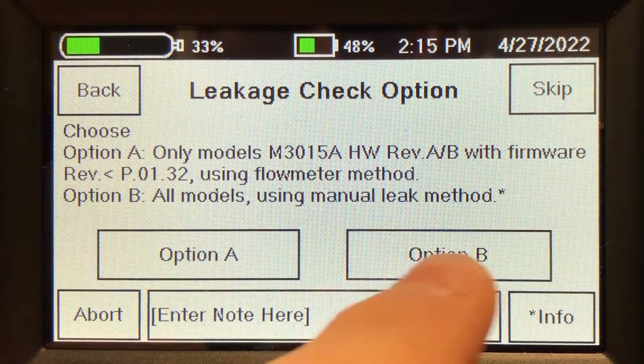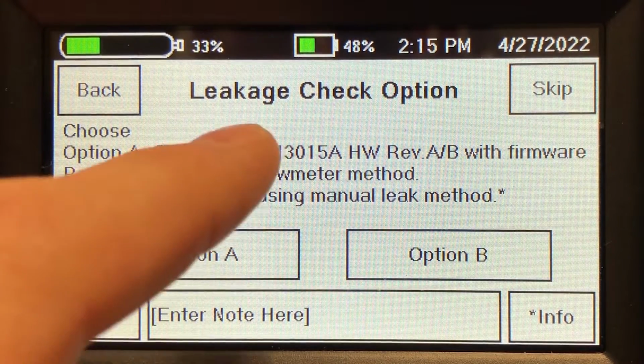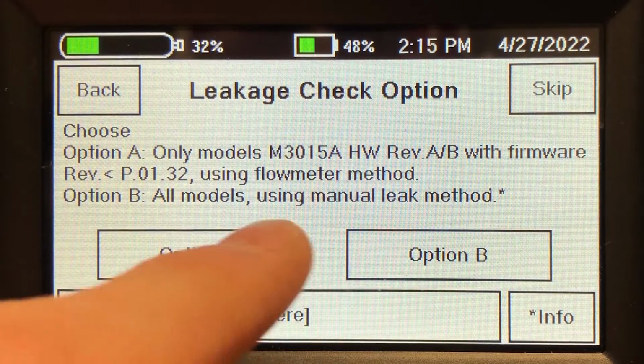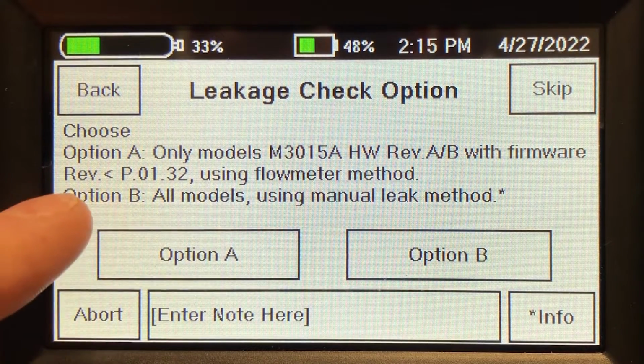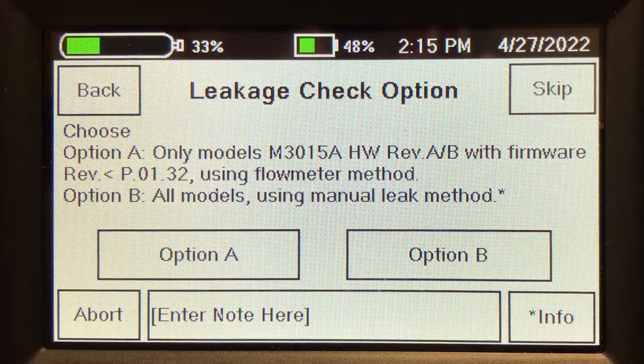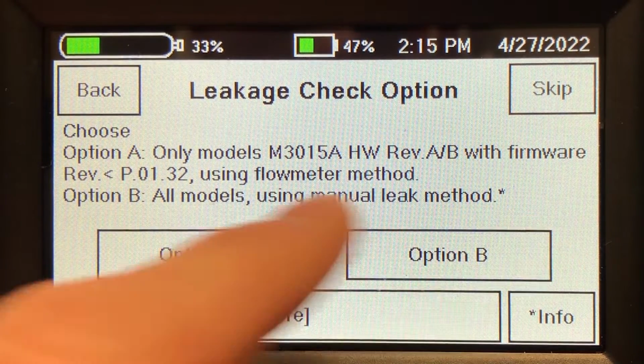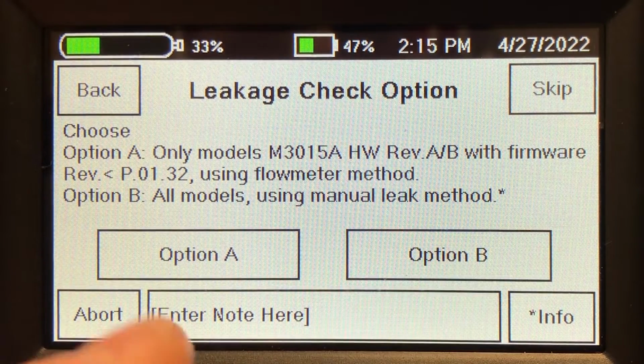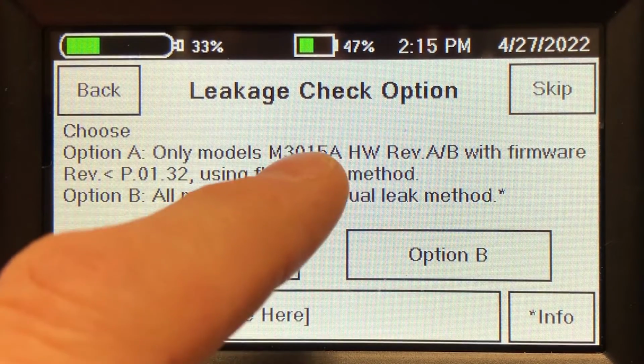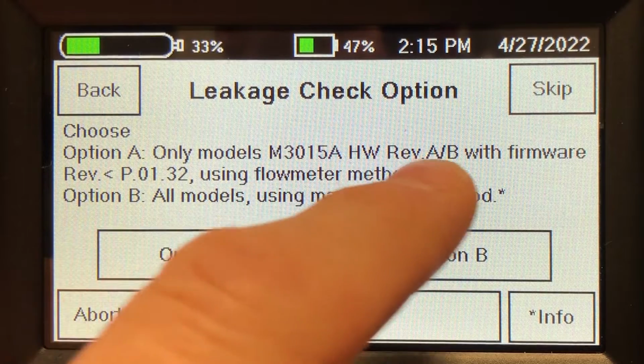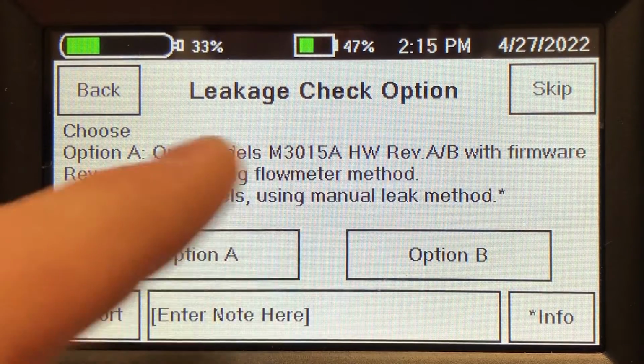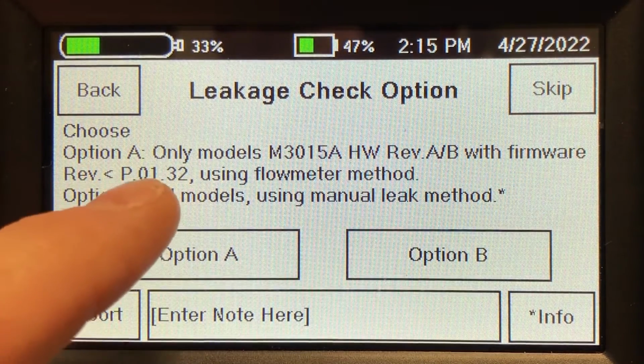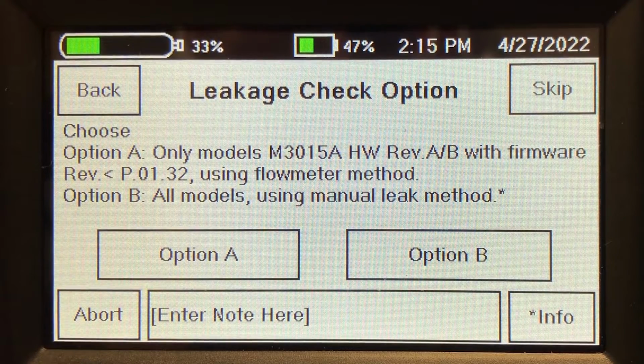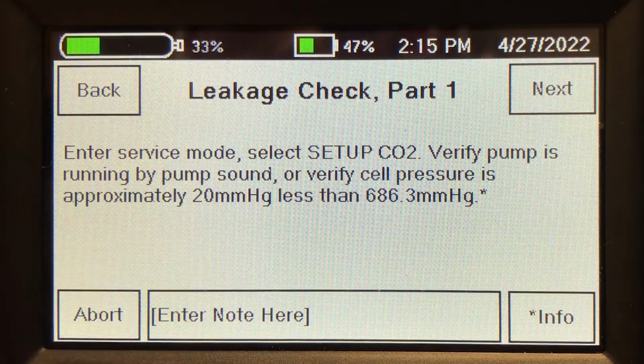In the user manual, it gives us two ways of testing for leak. With option B, you essentially take the device out, plug off its exhaust port, pressurize it, and measure how long it takes to leak down. You can do that method by touching option B. Option A is only good for M3015A modules that have revision A or B, with firmware revision 1.32 or lower. So we'll demonstrate that method.